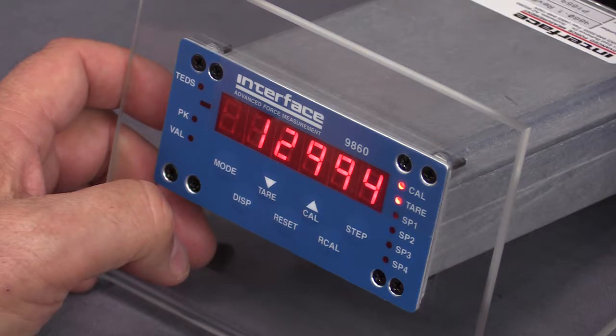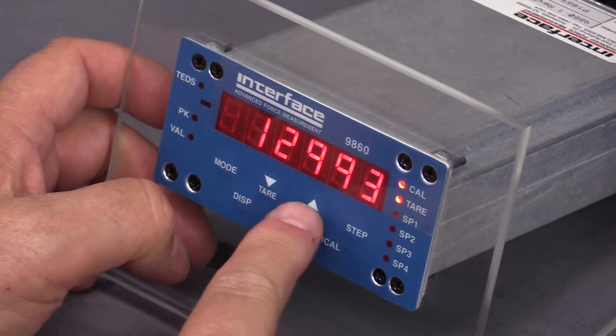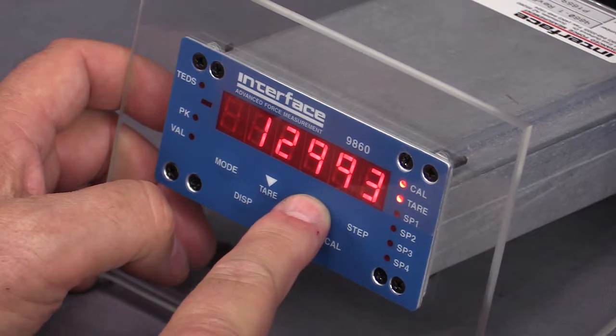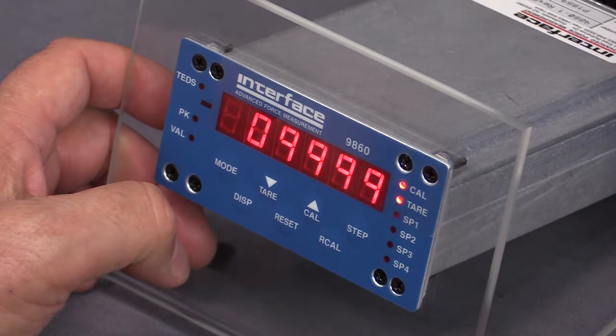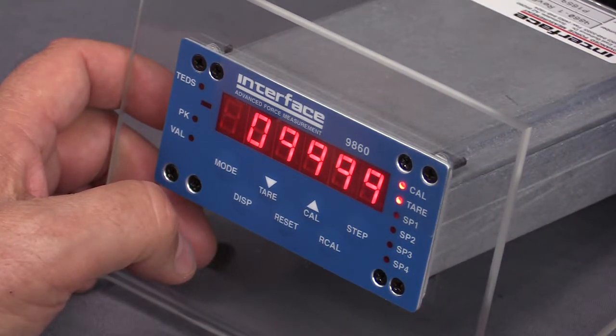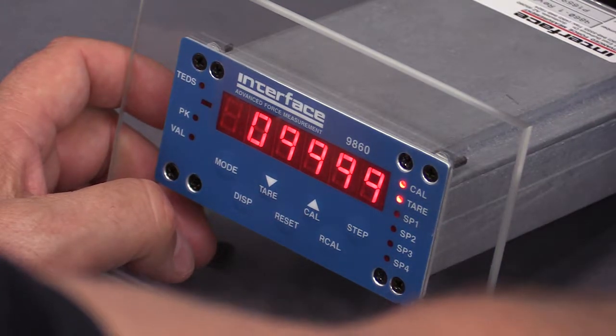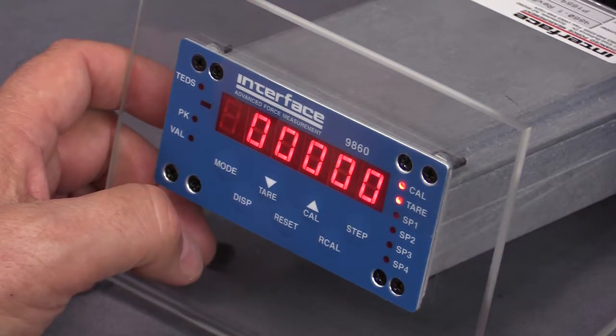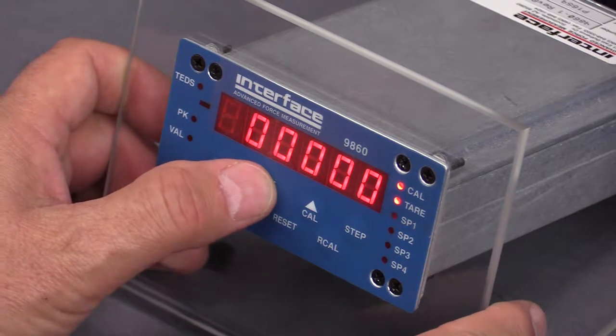We're putting on a load of two millivolt per volt, simulating that for a load cell. And now I'm going to hit the cal. When I do that, it captures that reading, so the two millivolt per volt now is associated with our full scale. I'm going to turn this back. Calibration is now complete. We're going to tare the unit.